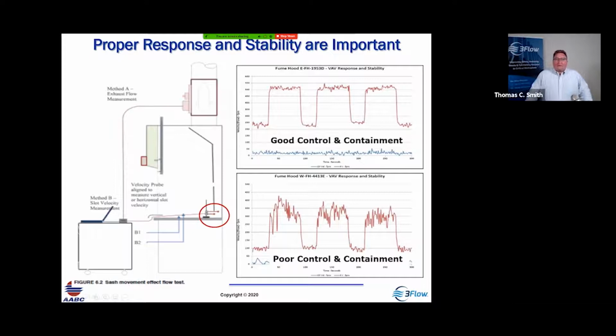If we look at 2 examples, sash is closed. We have a fairly high minimum flow. We open the sash. We can see it's repeatable between sashes open and closed. There's good containment in each of these conditions. However, the bottom one shows as we open the sash, it starts off fairly low. It's overshooting and undershooting, and it's not been tuned properly to control the flow.